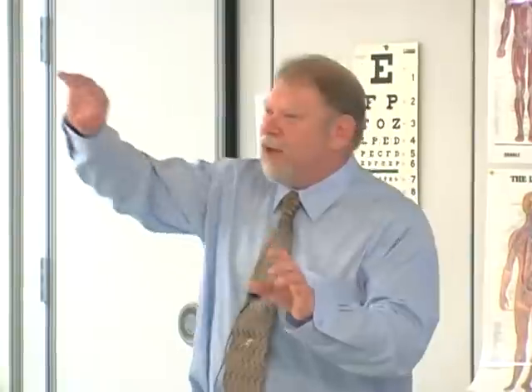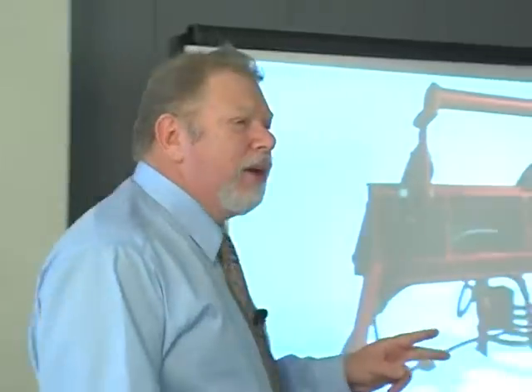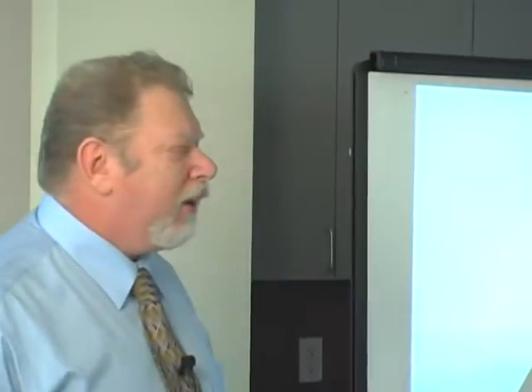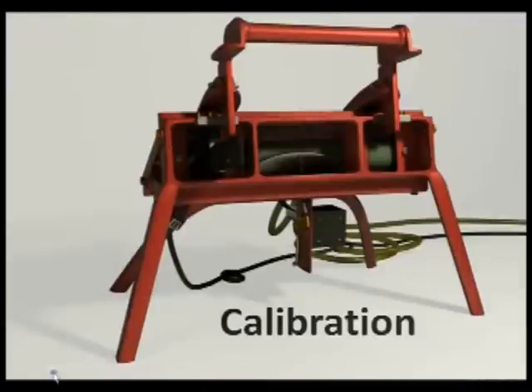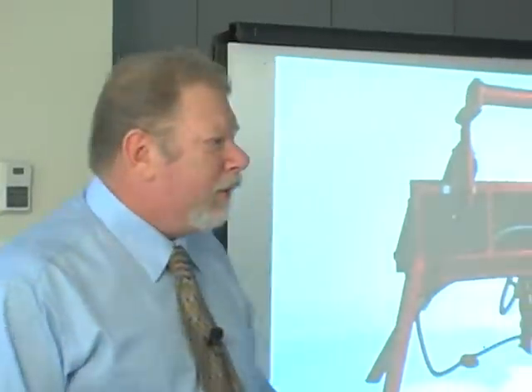The slope of the force curve is its flexibility. We then took the slopes of thousands of force curves and plotted them in a scatter graph, eliminated the outliers, and the trend line gave us a mathematical formula: if you take body weight and foot flexibility, I can tell you the range of forces — the correct slope of the force curve — for activities of daily living. This changed our life. We ran about a 20% failure rate until we developed this. Now we have a 0.9% failure rate.